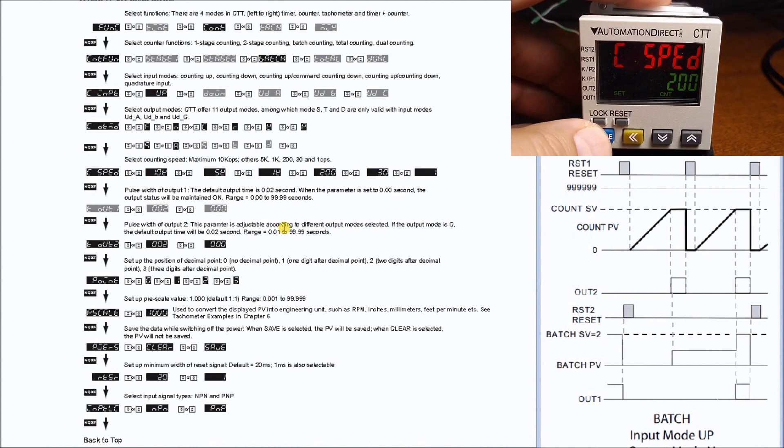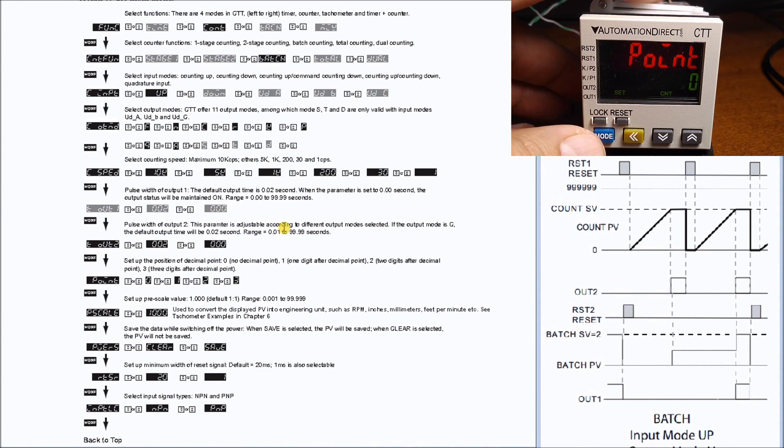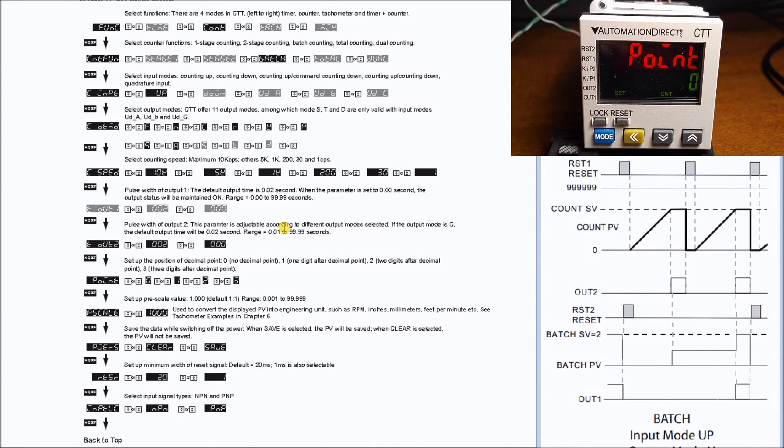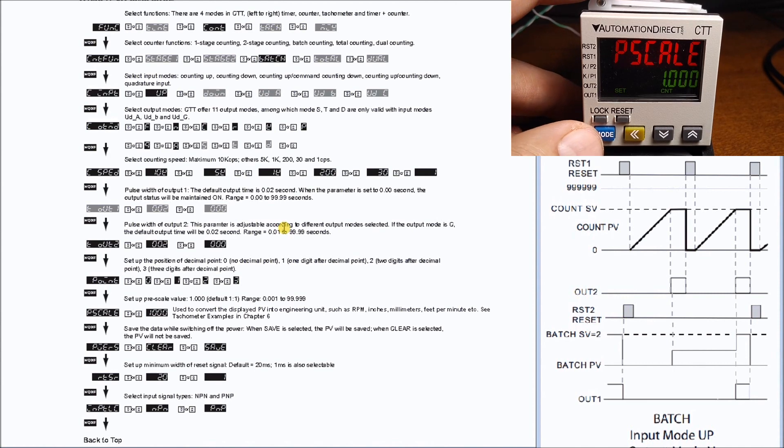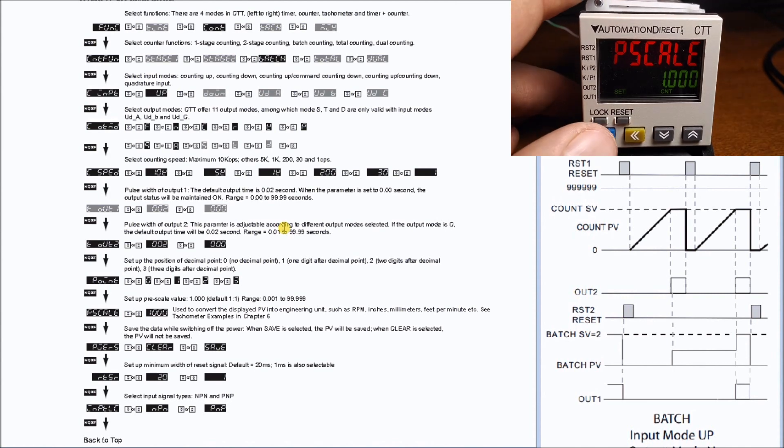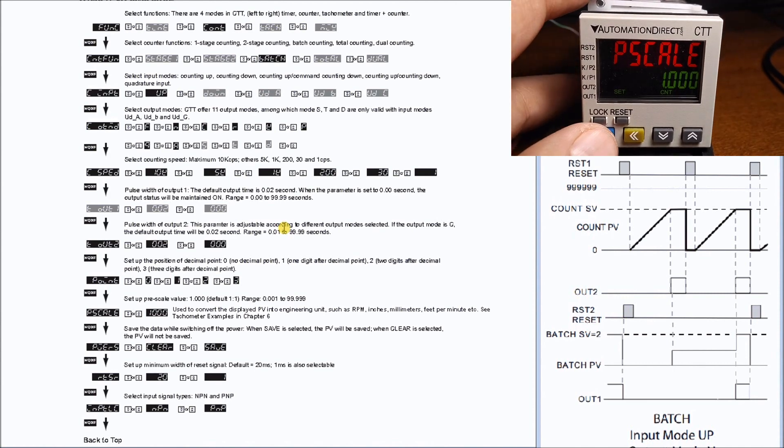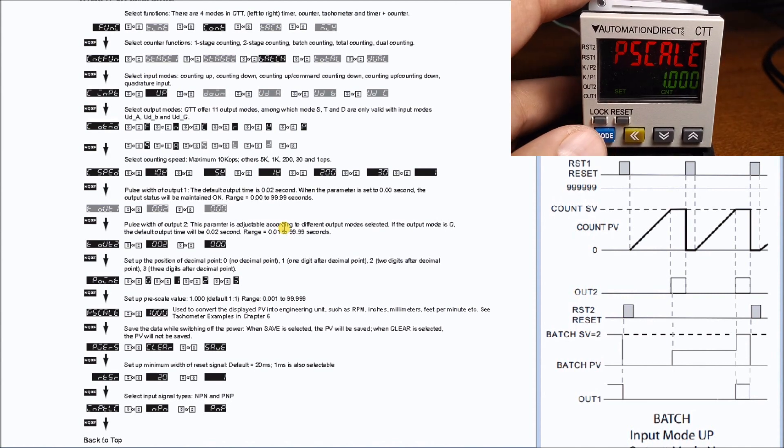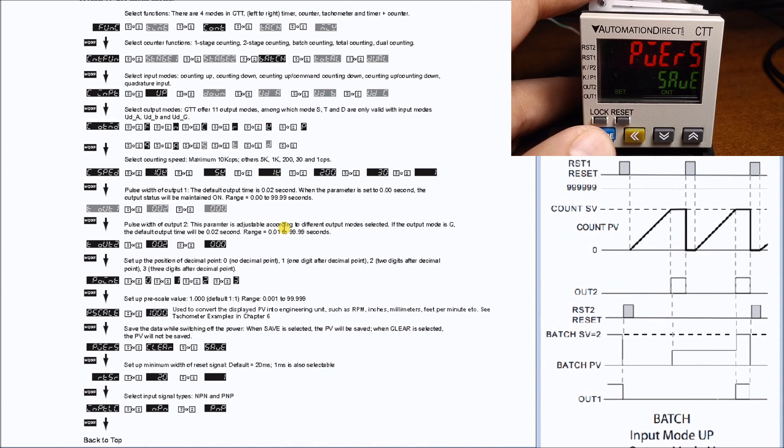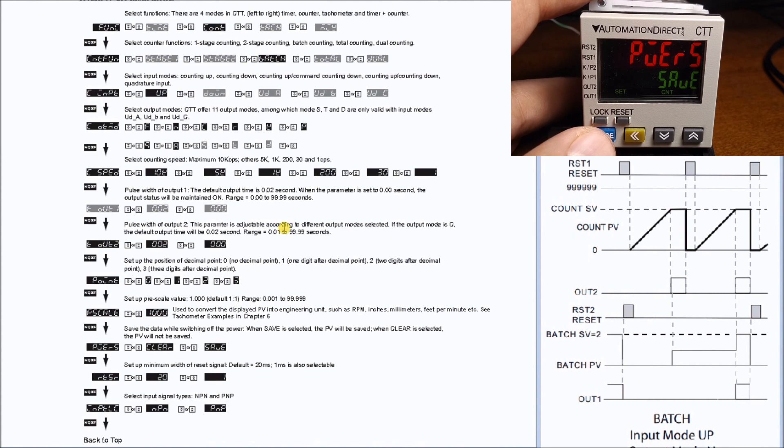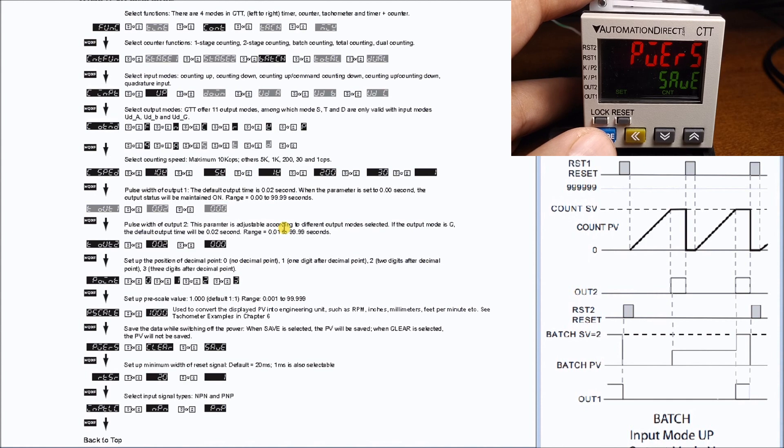Hit mode again and this gives us our decimal point. Mode again gives us our pre-scale. Again we can put engineering units onto the display screen so that we can display real values to the operator. Hit mode again and we have our power option. In our case here we have save, which means that our set values for our batch as well as our count value are maintained when the power goes off to the unit.